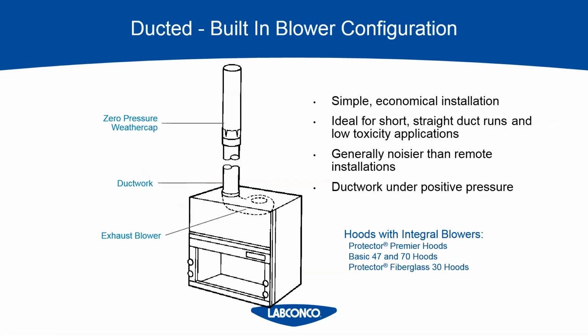So I always say to start with the remote blower configuration, and if you can't make that work and you have a short, straight duct run, then you can go with the built-in blower. Because this kind of setup is ideal for mobile lab spaces or single-story buildings with a pitched roof, where it would be really difficult to install a blower on the rooftop.